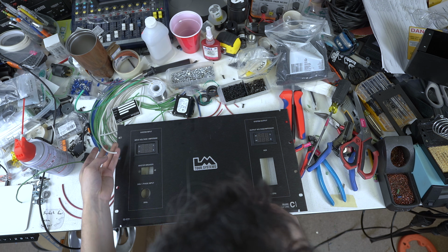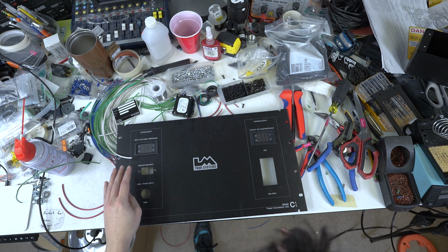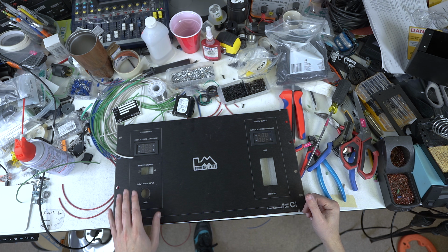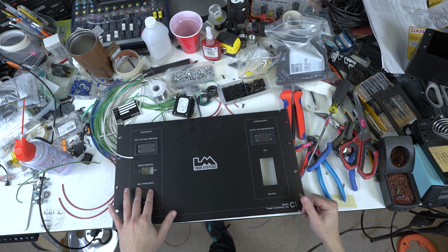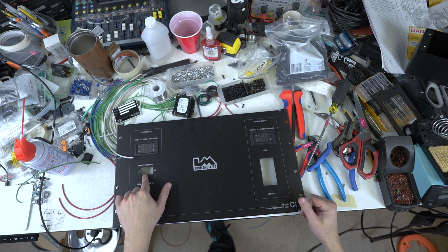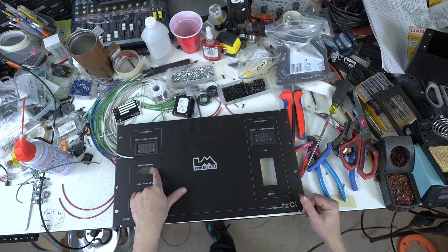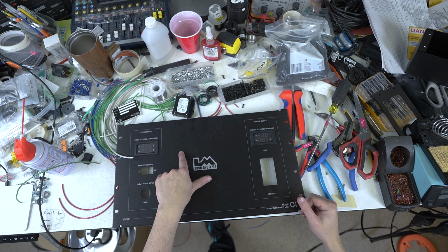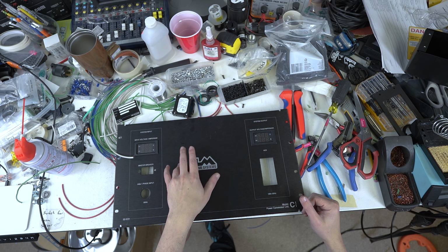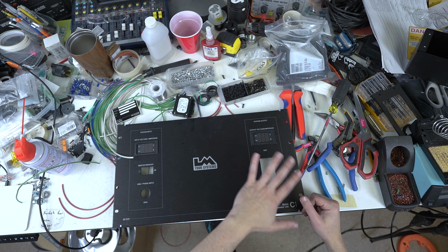So what I'm going to do is get the breaker wired in. Essentially this will run from the True 1 inlet to the line side of the breaker. The load side of the breaker goes to the line side of the transformer, and the load side of the transformer goes to all the devices.